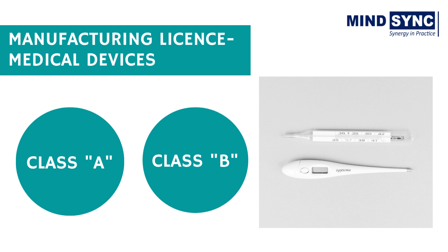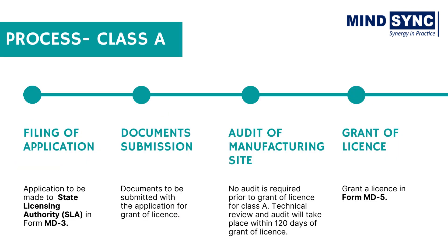Moving forward, I am going to tell you the complete process of obtaining a manufacturing license for Class A and B medical devices. Process for Class A medical devices: the first step is filing of application — application is to be made to the state licensing authority in Form MD3. Next is documents submission, to be submitted along with the application by the manufacturer. The next step is audit of the manufacturing site — no audit is required prior to grant of license for Class A medical devices; technical review and audit will only be conducted within 120 days of grant of license. And finally, grant of license — a license is granted to the manufacturer of Class A medical devices in Form MD5.